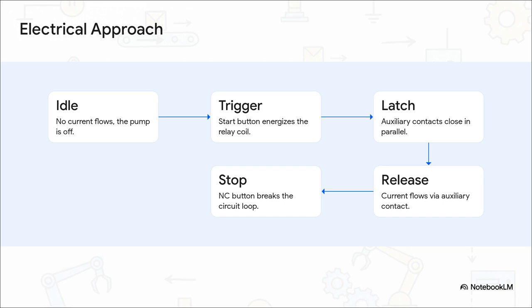It's self-holding. Finally, step 5, to stop the whole process, you press a totally separate stop button. That physically breaks the main power loop, drops the electricity, opens the contacts, and breaks the latch.